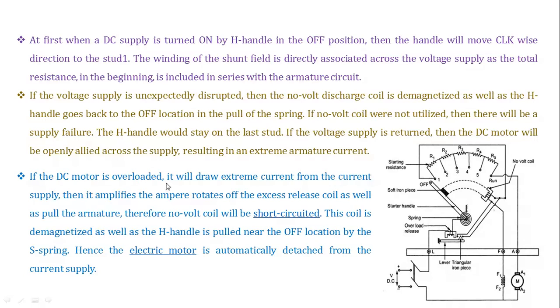If the motor is overloaded, it will draw extreme current from the current supply. Then it amplifies the ampere turns of the overload release coil and pulls the armature. Therefore, the no volt coil will be short circuited, and this coil is demagnetized, as well as handle H is pulled near the off location by the spring. Hence, the electric motor is automatically detached from the current supply.